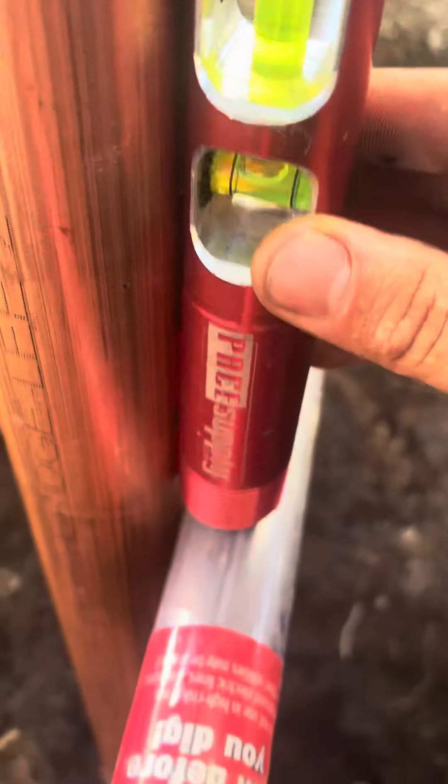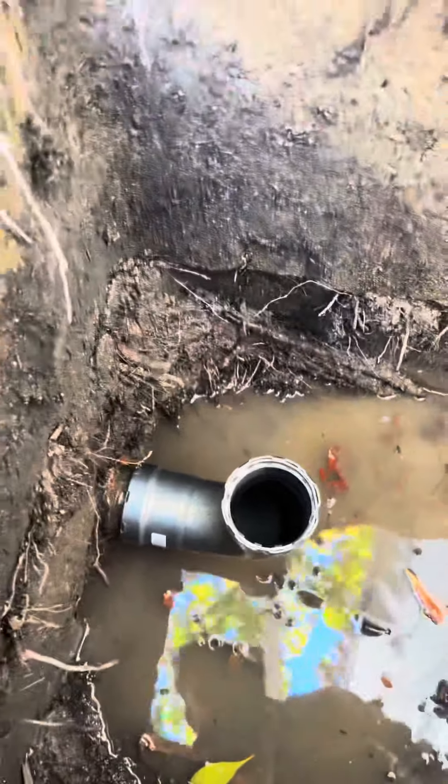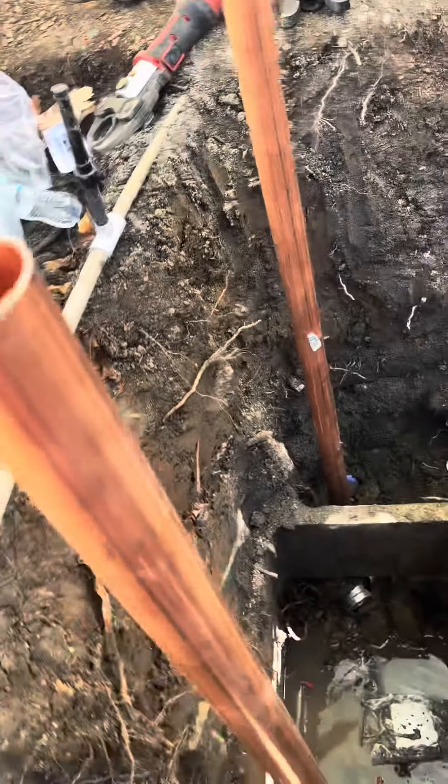This side is PVC, so I use a male adapter to press. The other side is going to be galvanized, so I'm going to be using MegaPress fittings. I'll do this 90 and then do the transition — six-inch brass and then a female adapter.